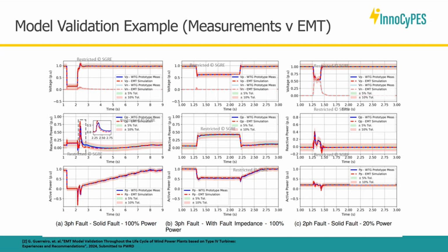So here's when the fault gets cleared, for example, and the power is ramped up. You're seeing positive sequence voltage and negative sequence voltage, positive sequence reactive current, reactive power, and positive sequence active power. The way the power ramps up after the fault is also specified by the grid code, with many specifications.